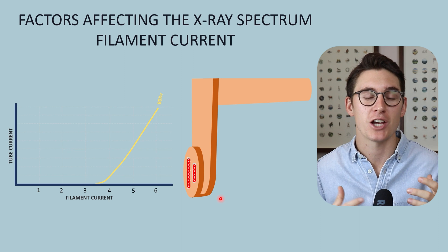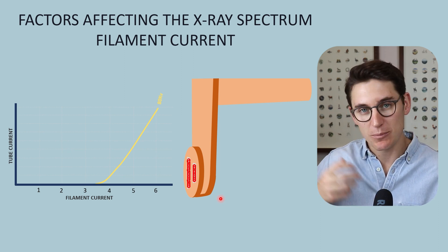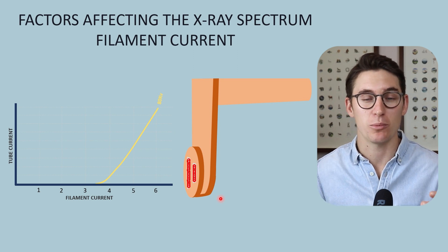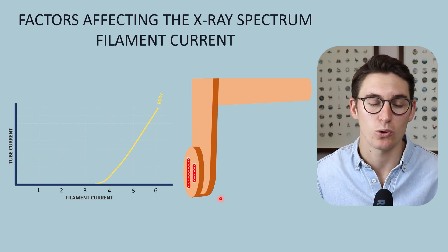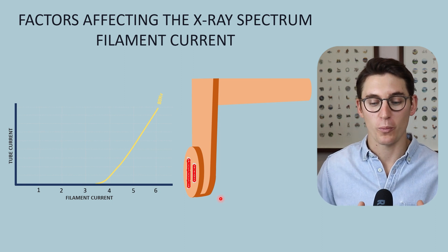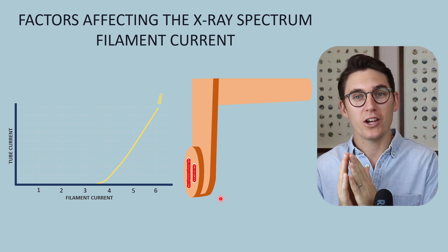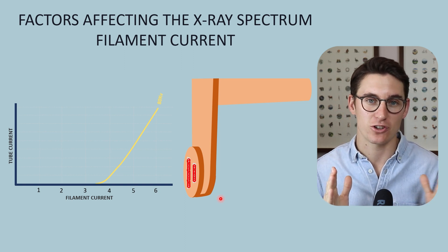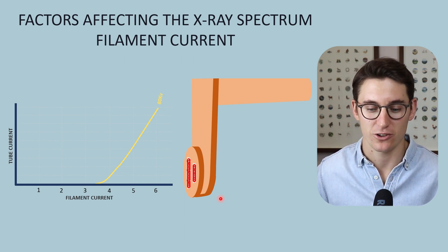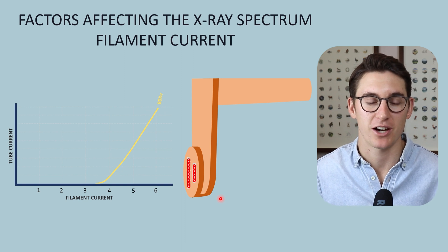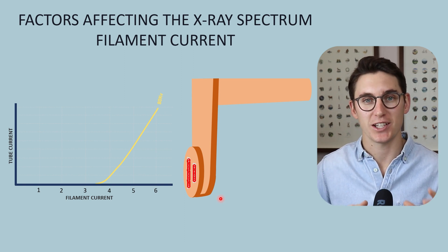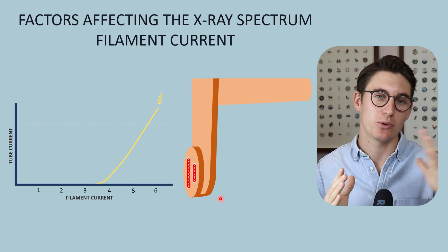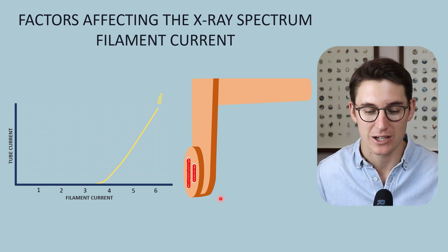The more current we run through that filament, the more heat is generated in the filament coil and the more electrons that are available to be accelerated towards our anode. We are not changing the energy of those electrons at the surface of our cathode by changing our filament current. The only thing we are changing is the number of electrons available — it's our tube potential that will then accelerate those electrons towards our anode.